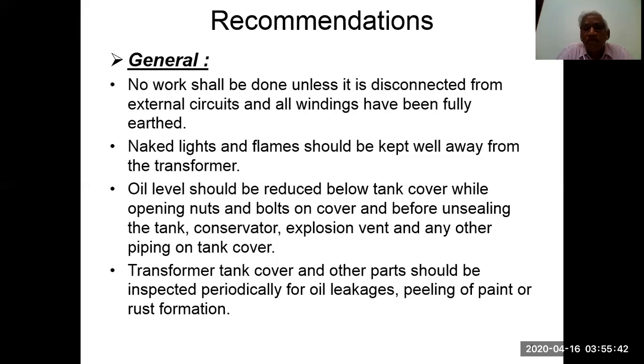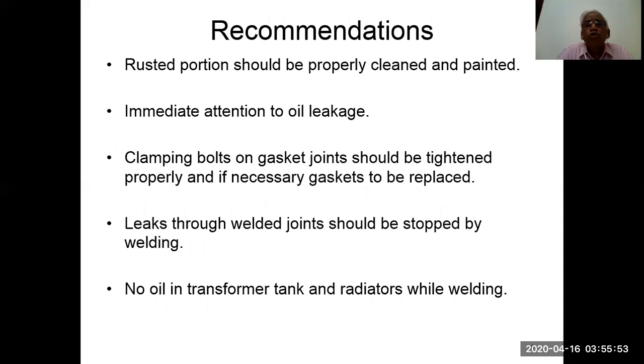Transformer tank cover and other parts should be inspected periodically for oil leakages, peeling out of paint or rust formation. Recommendations: rust portion should be properly cleaned and painted. Immediate attention to oil leakage. Clamping bolts on gasket joints should be tightened properly, and if necessary, gaskets should be replaced. Leaks through welding joints should be stopped by welding. No oil in the transformer tank and radiator while welding.